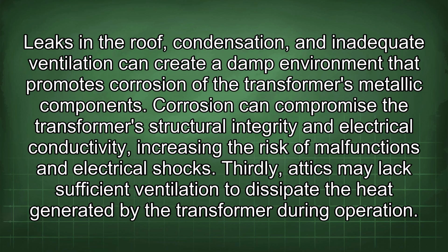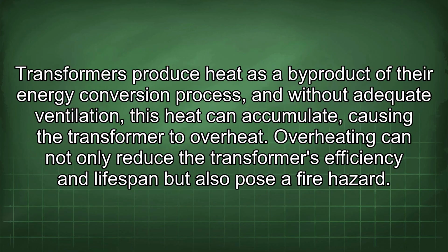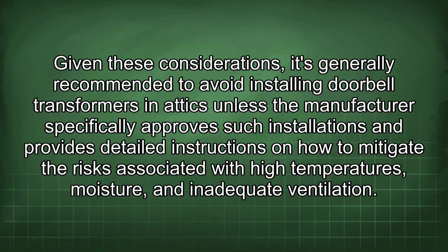Thirdly, attics may lack sufficient ventilation to dissipate the heat generated by the transformer during operation. Transformers produce heat as a byproduct of their energy conversion process, and without adequate ventilation, this heat can accumulate, causing the transformer to overheat. Overheating can not only reduce the transformer's efficiency and lifespan, but also pose a fire hazard. Given these considerations, it's generally recommended to avoid installing doorbell transformers in attics unless the manufacturer specifically approves such installations and provides detailed instructions on how to mitigate the risks associated with high temperatures, moisture, and inadequate ventilation.